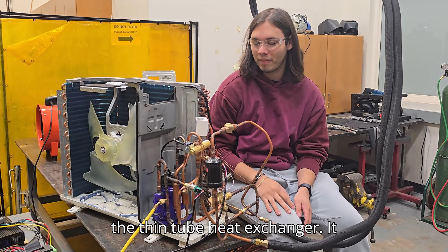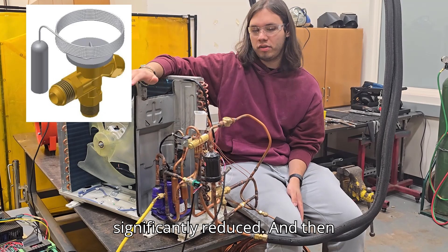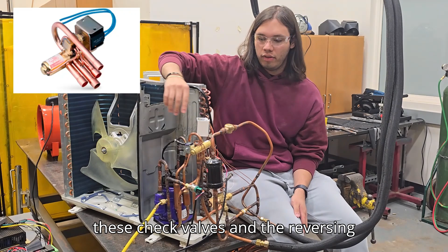The compressor will send the refrigerant to the fin tube heat exchanger. It will take the heat from these pipes and send it to the outside air with this fan. So the refrigerant will move through a filter dryer, which is right here, a sight glass, and a one-way thermostatic expansion valve where its pressure and the temperature will be significantly reduced. And then these check valves and the reversing valve will allow the refrigerant to flow backwards, which lets us change from heating to cooling mode.